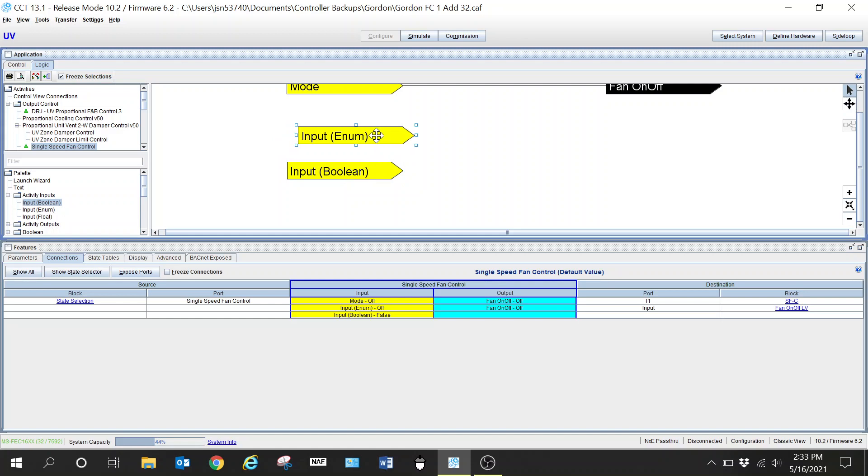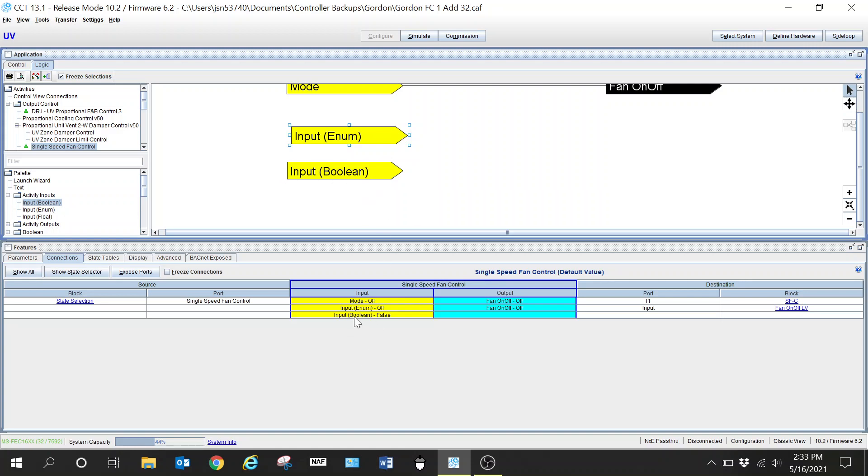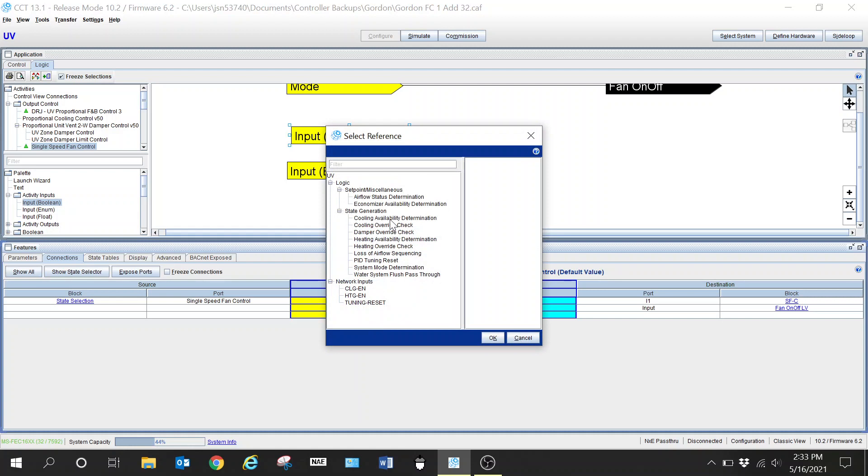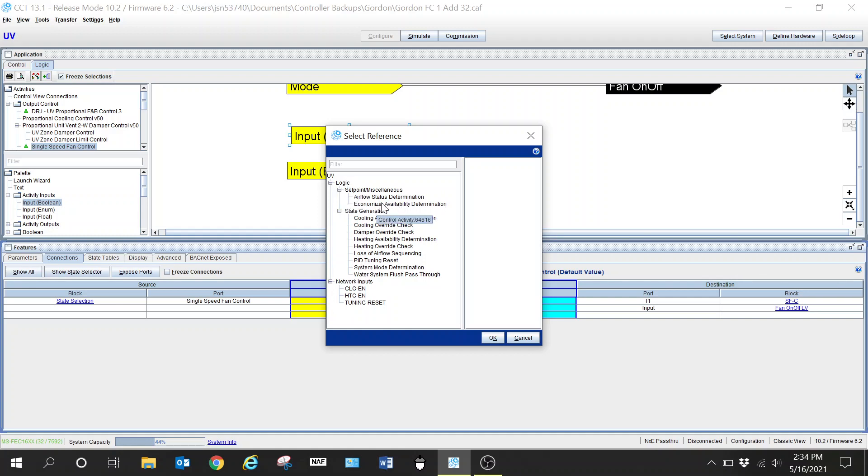Now we have both of these blocks connected. What we need to do is connect them to our low temp alarm input. So let's see what happens when I try to connect the boolean input. I'm going to right click, make a connection and it's going to bring up my pop-up window here. You can see there is no point that will match the state text within this device within CCT. I cannot match that low temp alarm. I can match some airflow status determination, things like that, things that are going to match this type of an input.